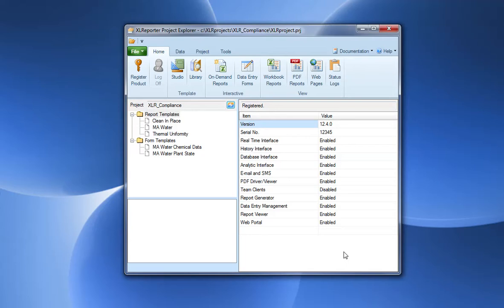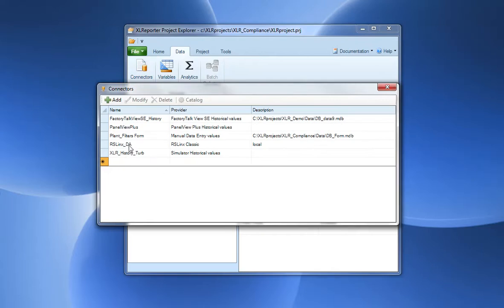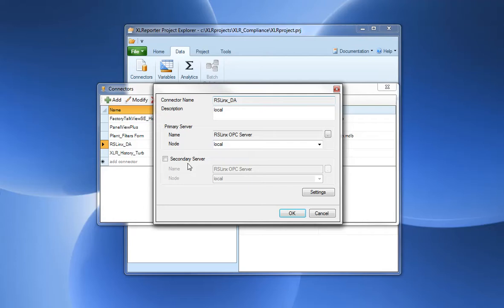The thermal uniformity report requires a data connector to a PLC. In this case I'm connecting to my local PLC through RSLinx. Notice that there's the provision to define a secondary server which is used if the primary server cannot be communicated to. This is an automatic transition by XLReporter.